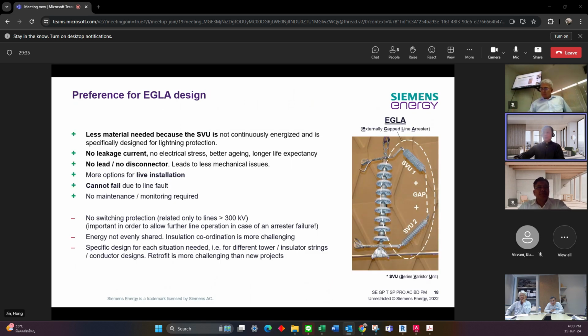So here is a short summary of the advantages of EGLA. The first one is cheaper and less material. The second one is no leakage current. The third one is no ground lead, and no disconnector is needed. And they cannot fail due to line faults. Also very important is that no maintenance monitoring is required because there is no leakage current. If you have a very big quantity of these surge arresters installed on the transmission line, the regular monitoring work is a very, very hard workload. If we use the EGLA, there is basically no necessity for monitoring. Then we can save a lot of workload for the operation.